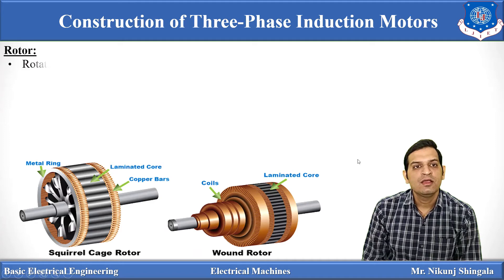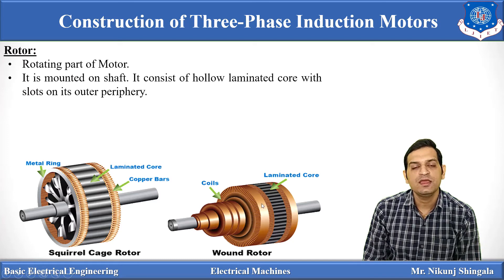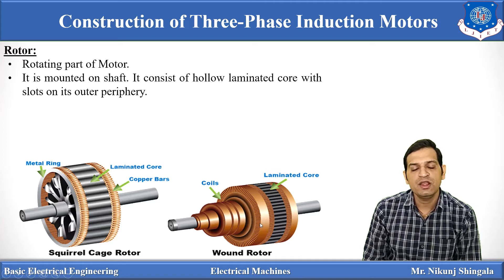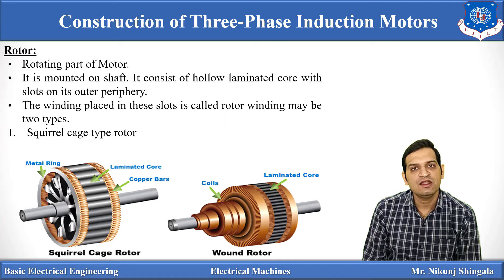The rotor is the rotating part of the motor. There are two types of rotor for the three-phase induction motor: the squirrel cage type rotor and the wound type rotor. It is mounted on the shaft. The construction of the rotor core is a hollow laminated core with slots on the outer periphery — whereas in the stator, slots are on the inner periphery. In the rotor slots, copper bars or windings are placed, called rotor winding. Based on the type of rotor winding, there are two types of rotor: squirrel cage type and wound type.